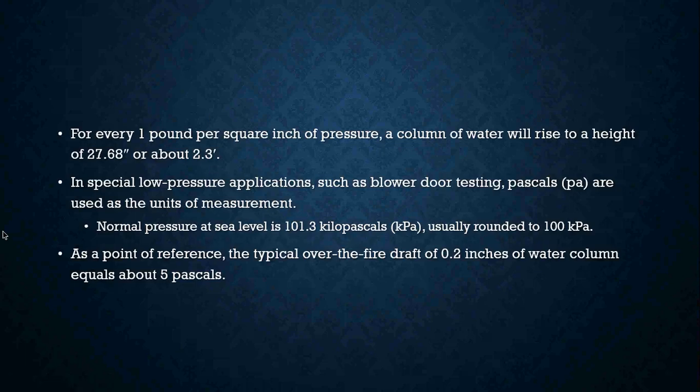For every 1 pound per square inch of pressure, a column of water will rise to the height of 27.68 inches, or 2.3 feet.